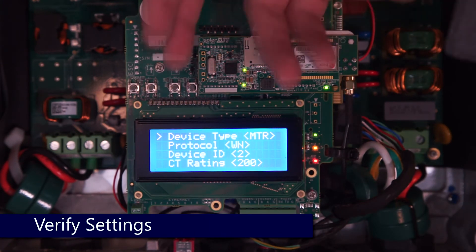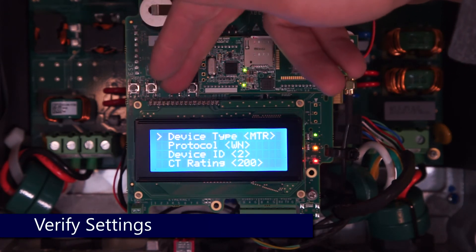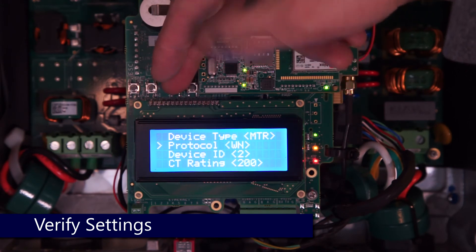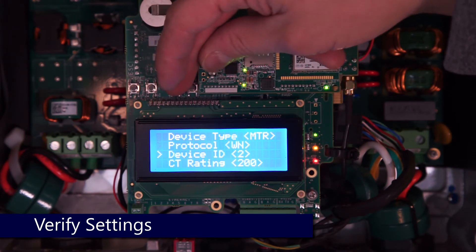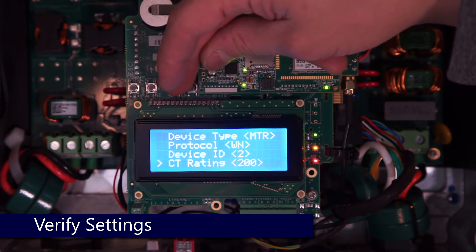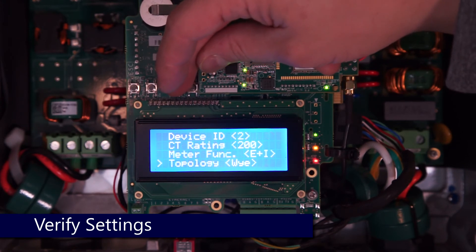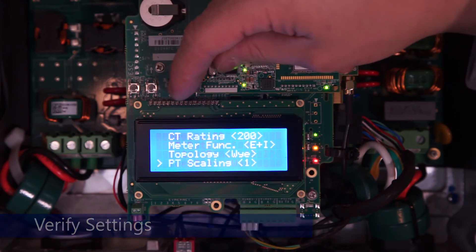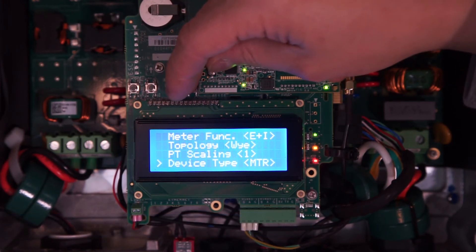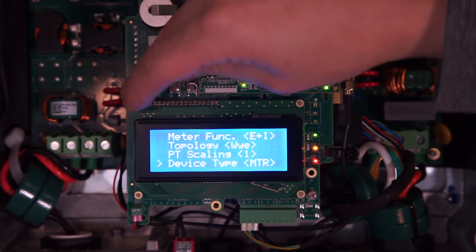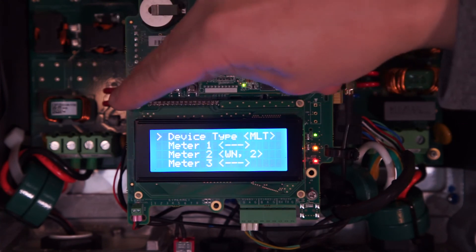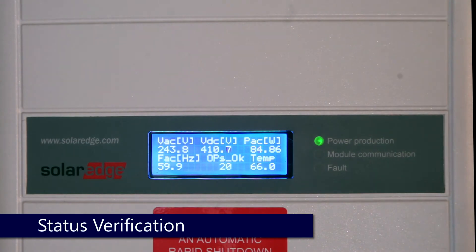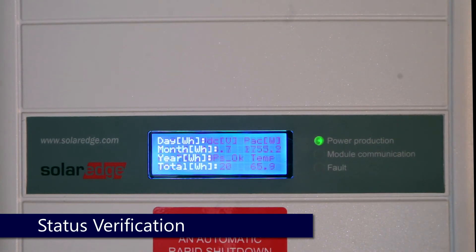After a quick scroll through to verify all of our settings are correct, we'll replace the cover, bring the inverter back up into production, and then go to the Import and Export meter status screens to verify all measurements are correct. To scroll through the status screens, just tap the green button underneath the screen.